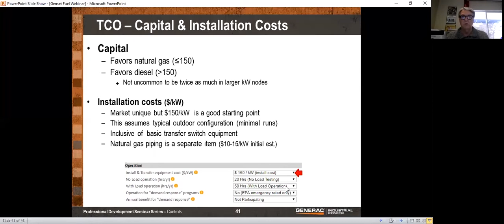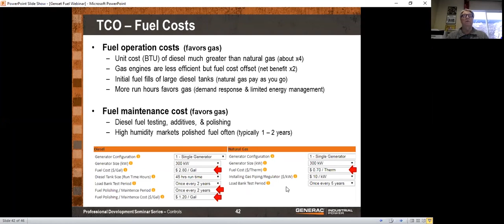The cost of a BTU of natural gas is typically about 4 times less than the cost of a BTU for diesel. Now, that's probably not the case now when Russia and Saudi Arabia are dumping fuel on the market, but typically that's about right. Gas engines are less efficient. We generally say, just as a rule of thumb, that you can generate a kilowatt of power with natural gas for half the price that you can generate a kilowatt of electricity on diesel. So you actually are getting long-term savings every time you turn that generator on because you're paying less for the fuel.